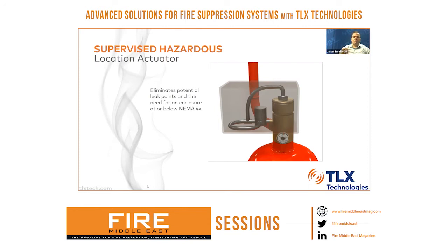you also may have to worry about putting an enclosure around the system to keep any of that gas material that might have propagated into the device, once there is an electrical signal sent to the system, from causing an explosion, if you will. It keeps that explosion contained within the system.